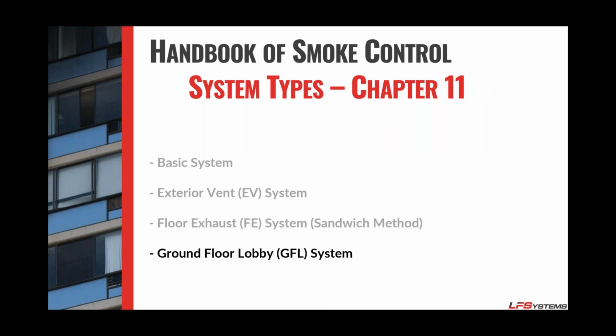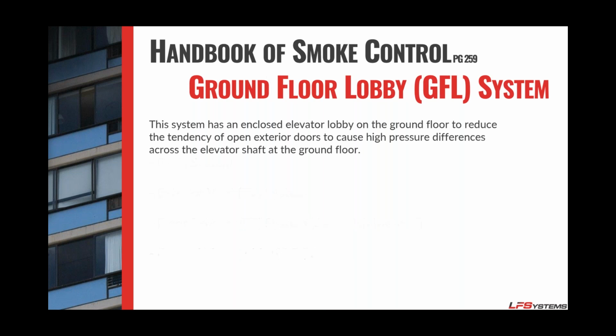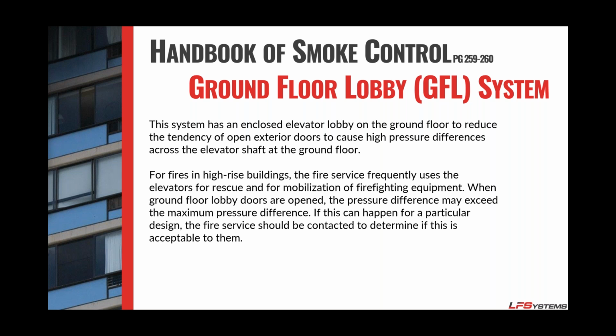So let's talk about the final one, which is called a ground floor lobby system. Obviously, this system requires you to have a ground floor lobby, kind of in the name, right? So it does, however, have some potential for high pressure at the lobby doors. And ASHRAE actually mentioned that if this type of design is used, you need to contact your local fire marshals to make sure that these pressures at the lobby door are acceptable.